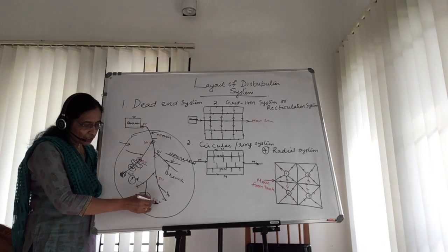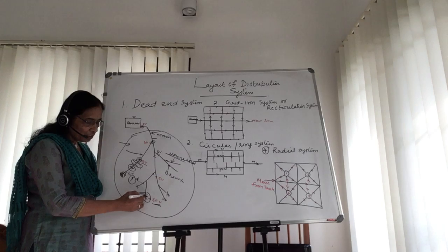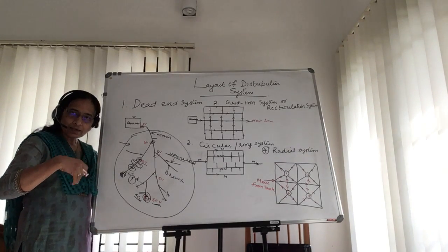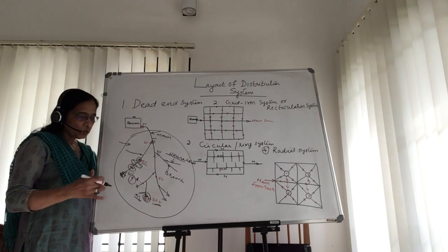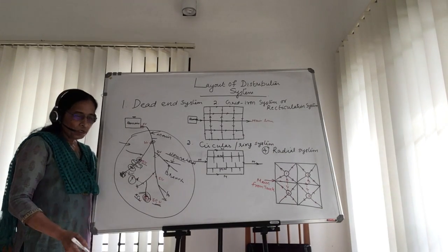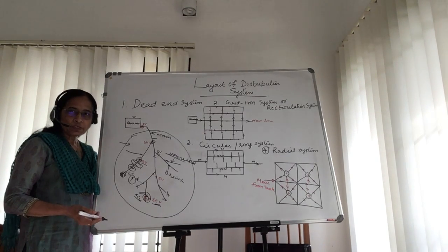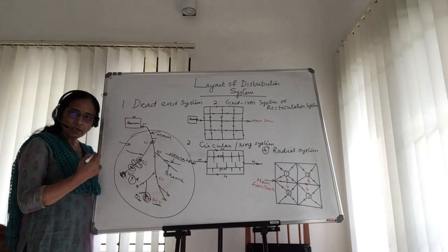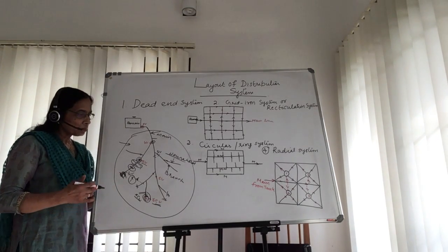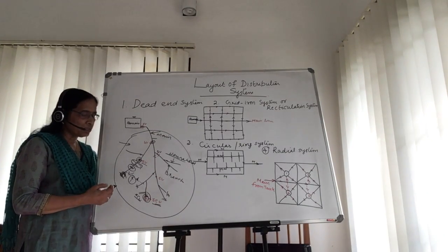You have to provide scour valves so that you can open this valve and discharge all the contaminated water through this valve. That means the number of scour valves is also more, is it? Or you have to cut open the line and then discharge the water. So those types of difficulties are there in maintaining the system.